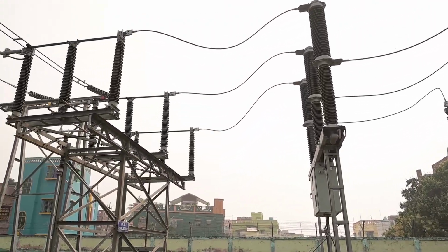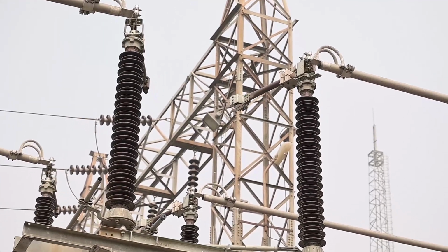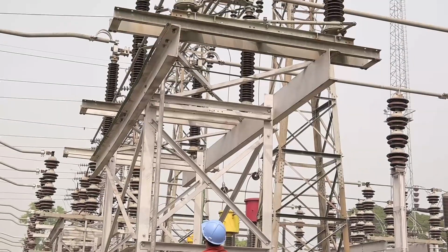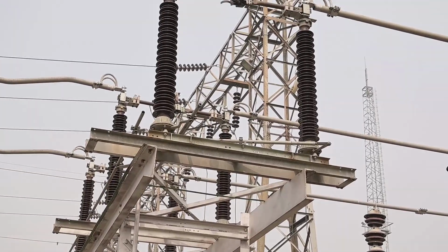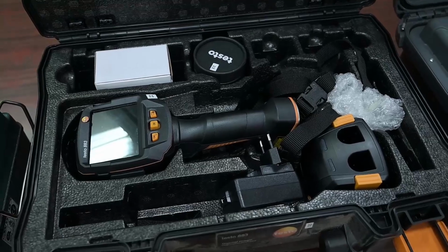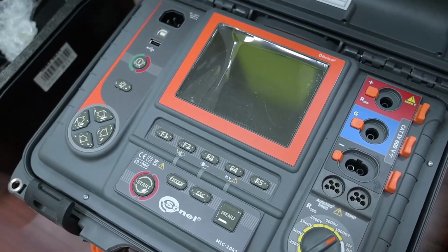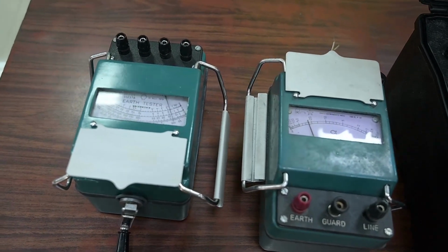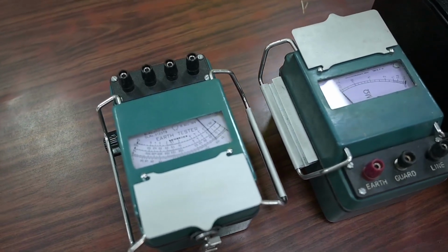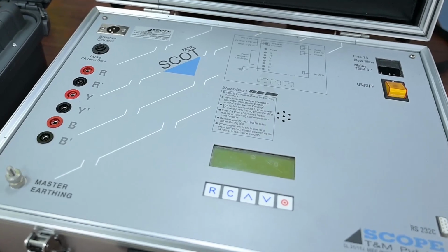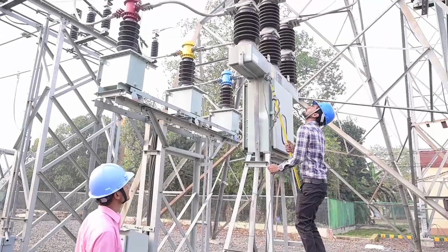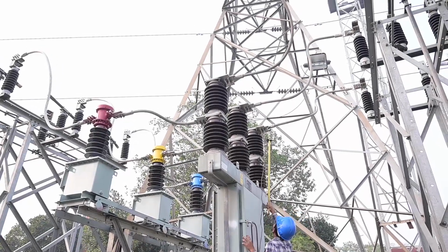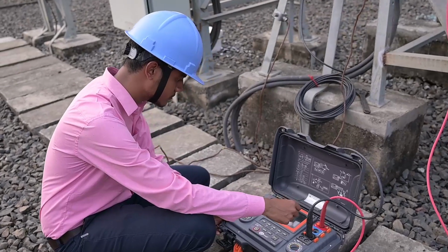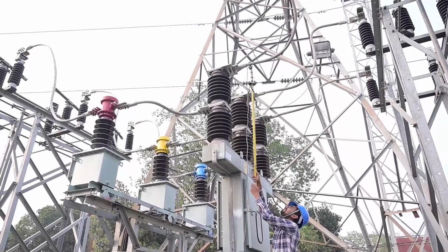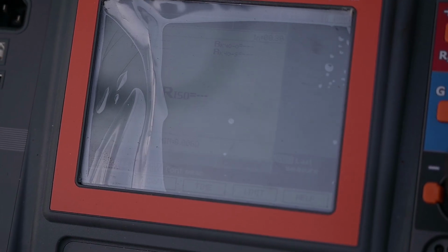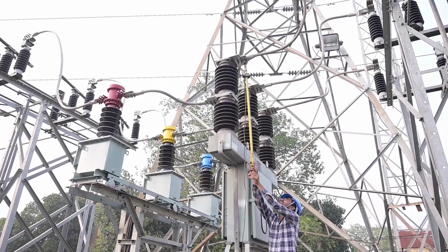We follow our periodic maintenance and condition monitoring as per the guidelines of WBSETCL. To achieve this objective, we use different testing equipments provided by our department such as thermovision camera, Tan Delta test kit, leakage current measurement kit, circuit breaker timer test kit, partial discharge analyzer, digital IR kit, high voltage detector, etc. DGA and routine tests are performed by the nearest testing department as per the maintenance schedule of WBSETCL. Time-based preventive maintenance of the substation equipments is carried out, and standard operating procedures are duly followed.